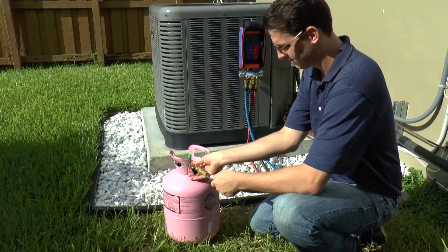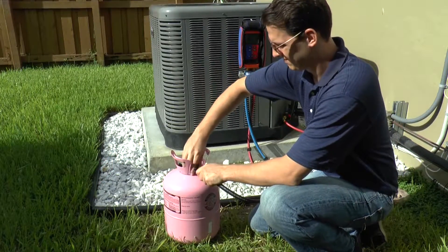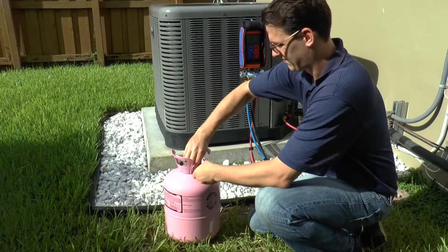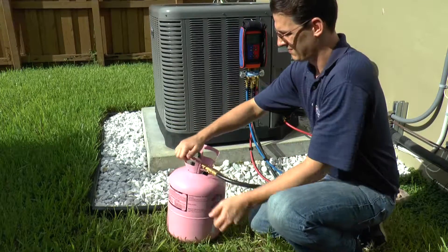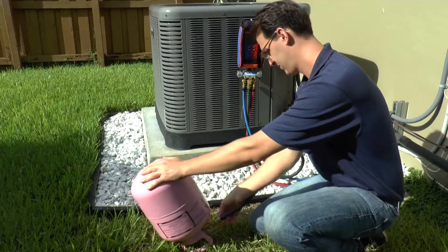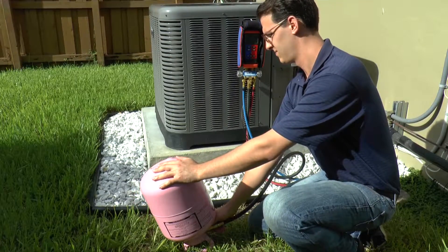Connect the black 3/8 inch hose with the ball valve closed to the refrigerant cylinder. If this is a new installation, open the high side and low side condenser service valves. Open the ball valve on the black 3/8 inch hose and the refrigerant cylinder valve. Then turn the system on.